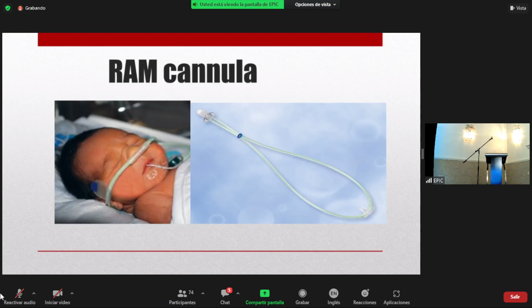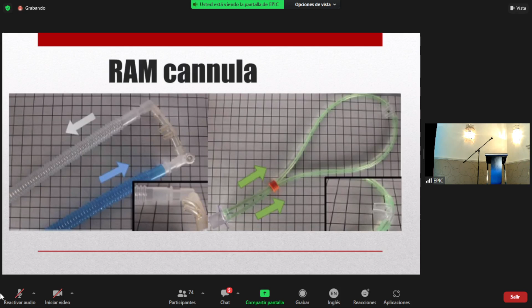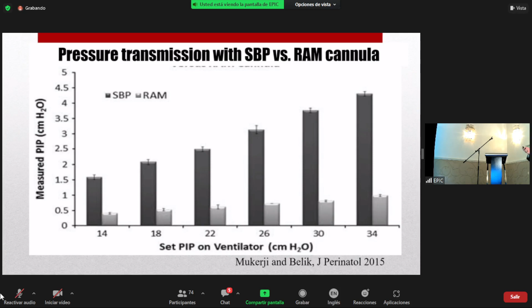And this is the point here. With the CPAP circuit: inspiratory limb, prongs, expiratory limb. With the RAM cannula, it's all just flow one way. And so you can't get a tight seal, because if you got a tight seal, you'd blow up the baby. So it's not a real efficient way. And the pressure transmission through the RAM cannula is really poor. So I don't need to waste my time, because people don't use it. So continue to not use it. And if somebody tries to get you to switch, please don't, because it's a really bad interface.